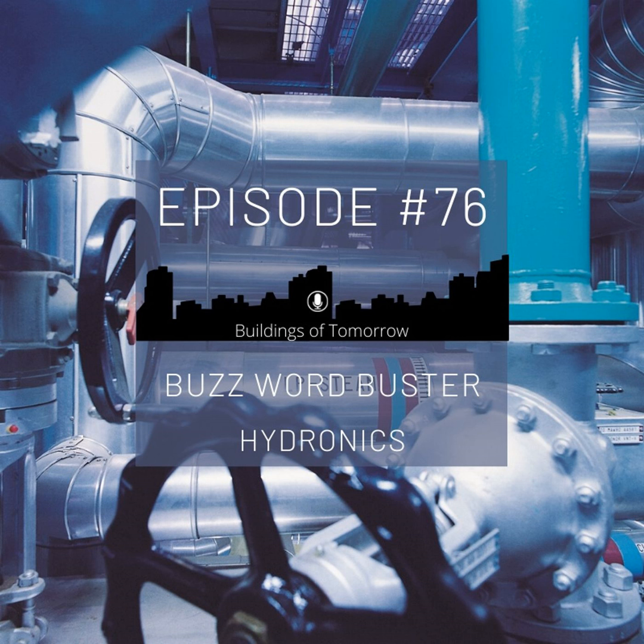But what we find, unfortunately, is that it's very often not done properly, because if you want to do it in a big system in a proper way, it needs time, and people are always crunched for time. So that's one of the things that is left out, and people just hope and cross their fingers that we get enough warm water or enough cold water to our consumers. And if that happens, nobody will make any bad comments about it. But what we then find is very often we lose on the energy efficiency side. So yes, the room gets warm. Yes, the chilled water goes out to the air handling unit in a sufficient amount, but it's not in the best energy efficient way. And that's why hydronic balancing is an important key part.